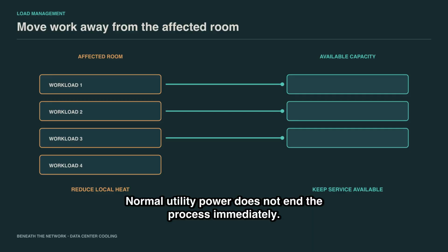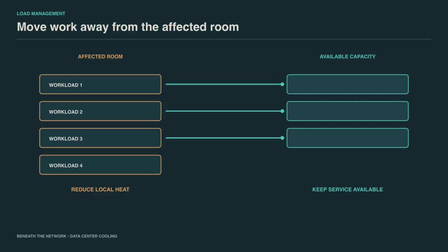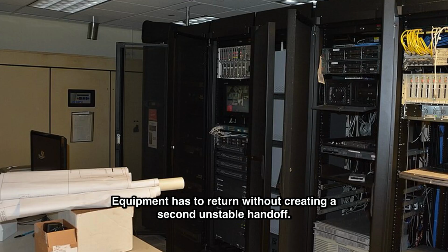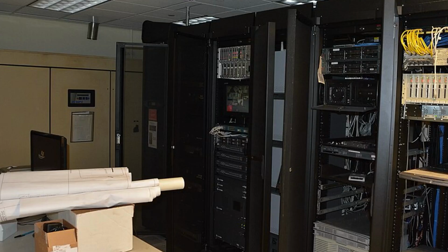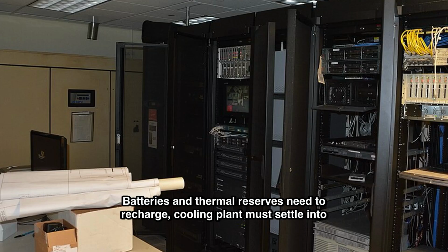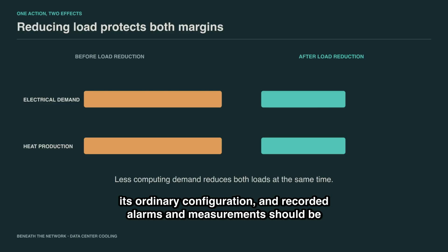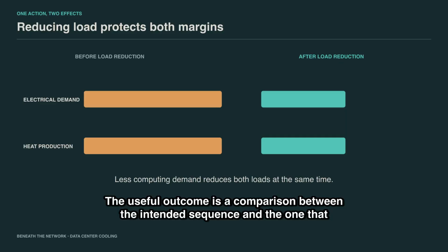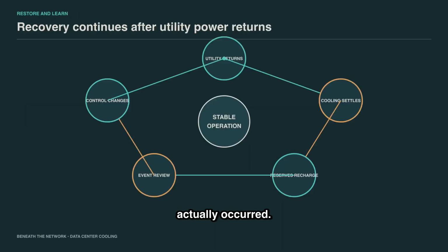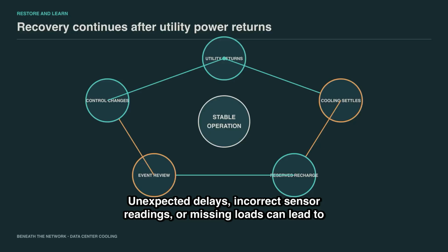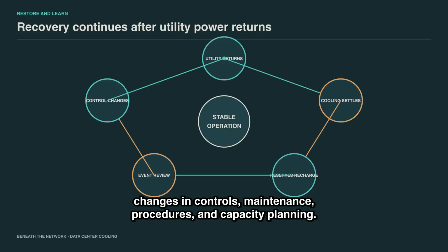Normal utility power does not end the process immediately. Equipment has to return without creating a second unstable handoff. Batteries and thermal reserves need to recharge. Cooling plant must settle into its ordinary configuration, and recorded alarms and measurements should be reviewed. The useful outcome is a comparison between the intended sequence and the one that actually occurred. Unexpected delays, incorrect sensor readings, or missing loads can lead to changes in controls, maintenance, procedures, and capacity planning.